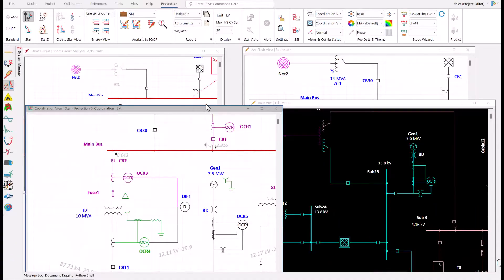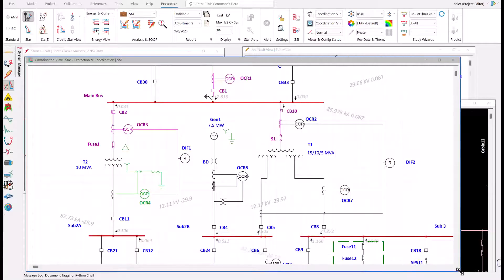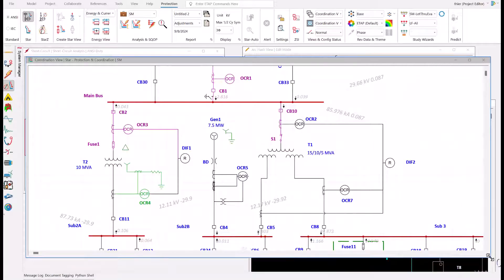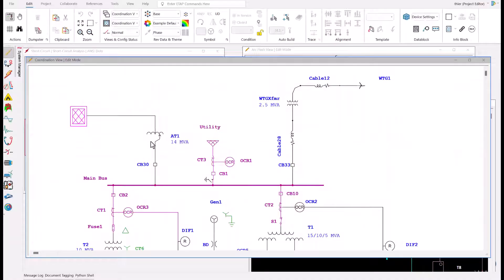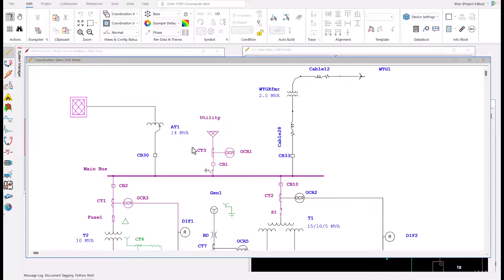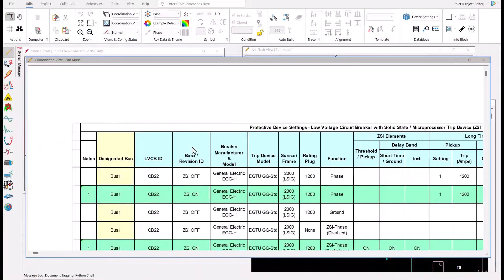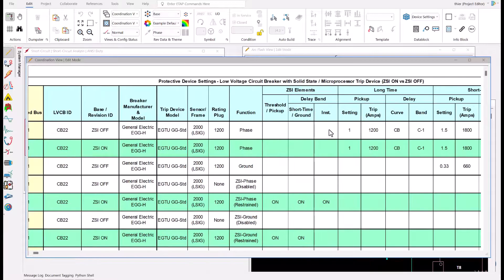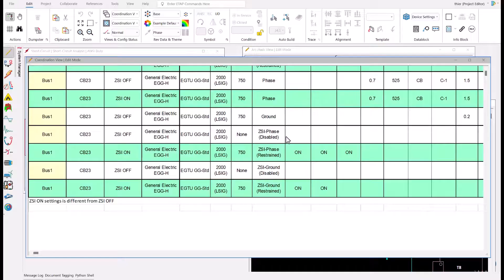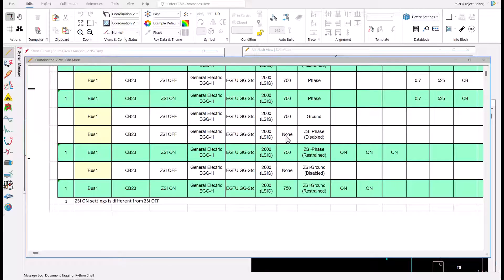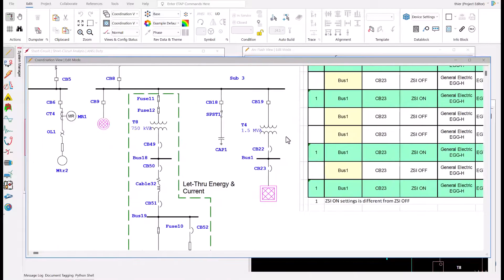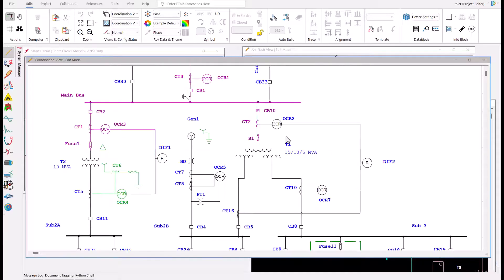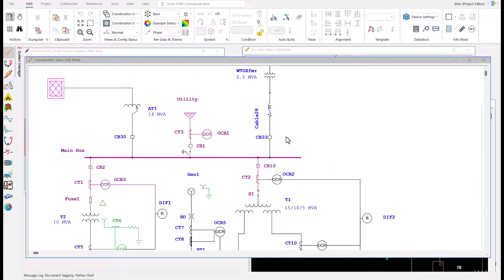Next, we move on to coordination and protection windows. Notice the difference in layout between the short circuit studies and the coordination windows. I inserted some breakers in the one line. Unlike short circuit, we need breaker devices for this study. Do you see that you don't even have to read a long report to see breaker settings? Everything is visible on the one line. That is fantastic for the audience. Life is made easy.